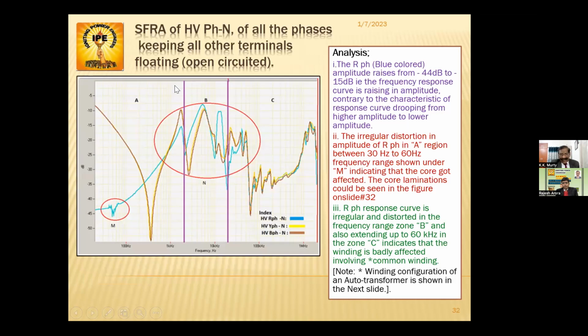So here, this is the core area. Okay, so you can see this in this core area. Conventionally the curve should come like this. This is the curve of the other two phases, whereas this is the curve of R phase. You can see the distortion here, and contrary to this, the curve, instead of drooping down, is going up. You can see this is the R phase, blue colored, amplitude rises from -44 dB to -15 dB. That is, the frequency response curve is rising in amplitude, contrary to the characteristic of the response curve, drooping from higher amplitude to lower amplitude.